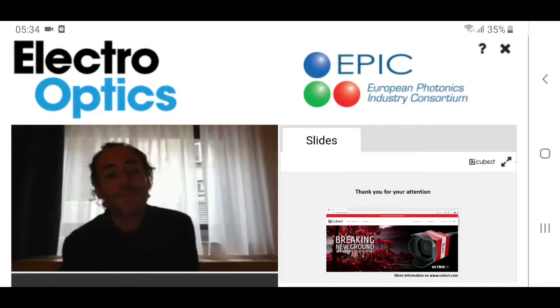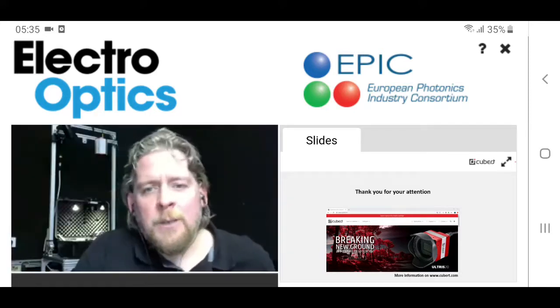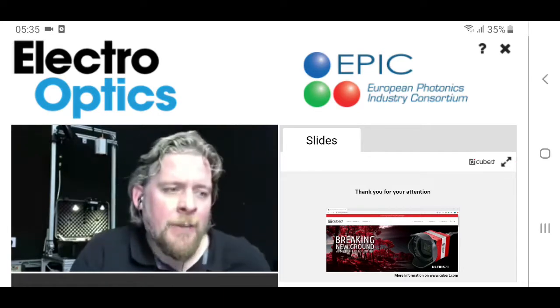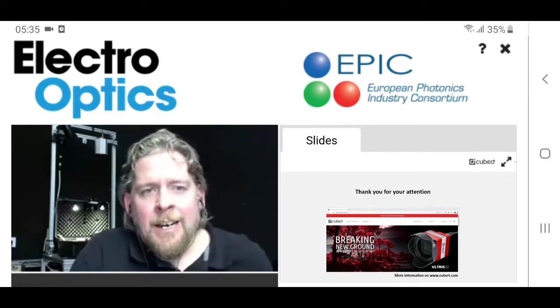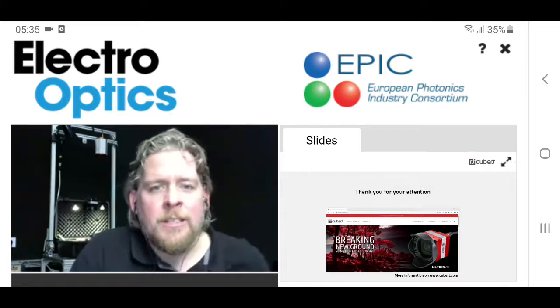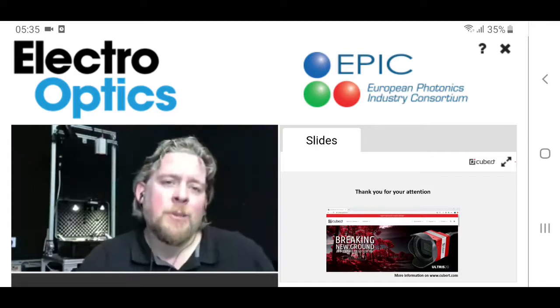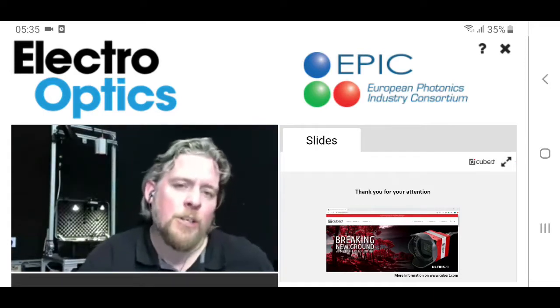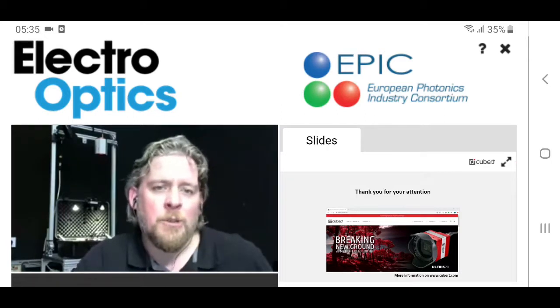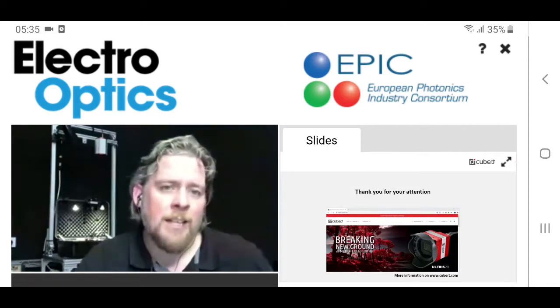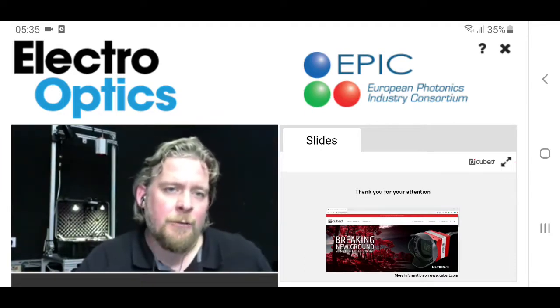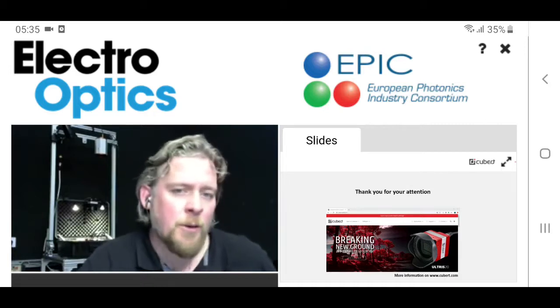Okay, typically in our software suite, you have the possibility of an automatic exposure time correction, which also takes care of the referencing for the white standard. So typically that should work out of the box. Everybody who's working with spectral images knows that as soon as you have big deviations in exposure time, that might introduce some errors, and you have to be cautious with that. But for, let's say, moderate deviations like a factor of 2 or 3, that should work out of the box already.